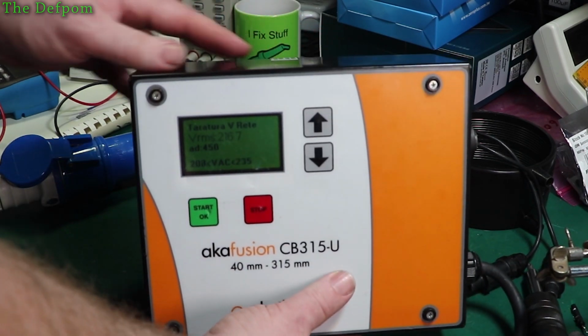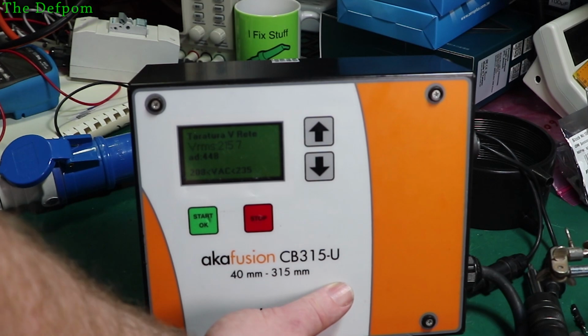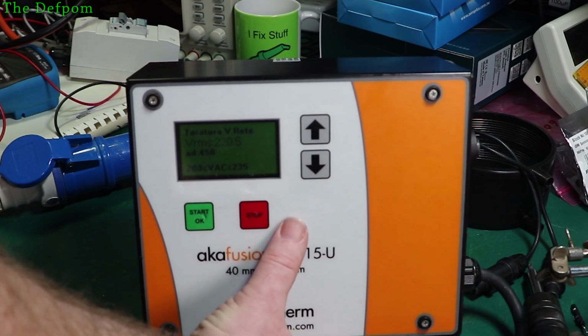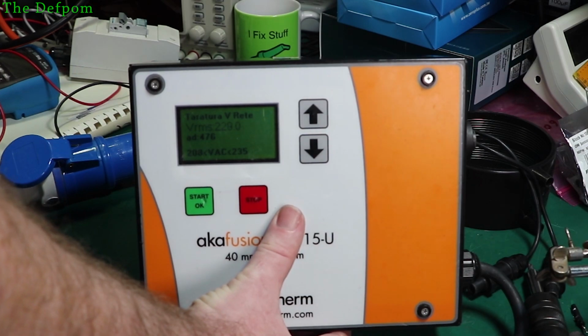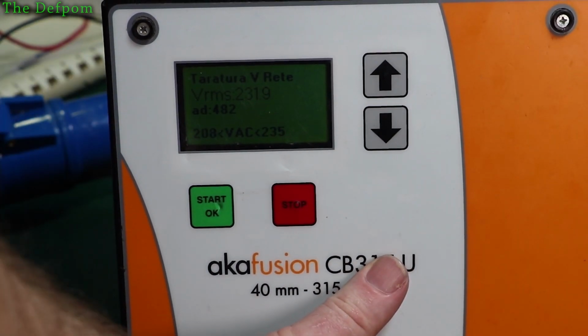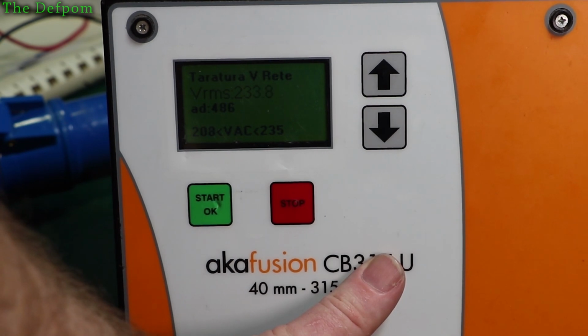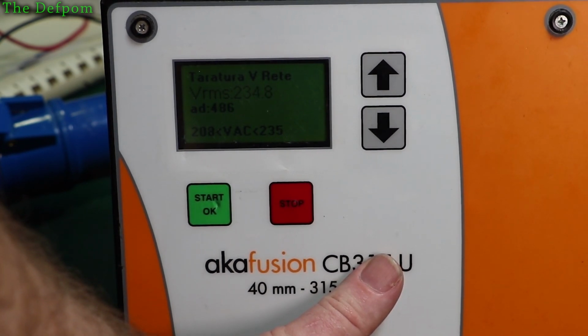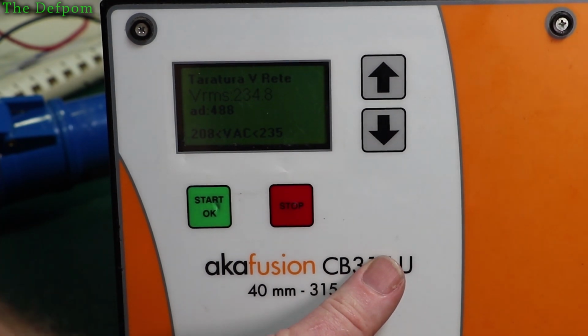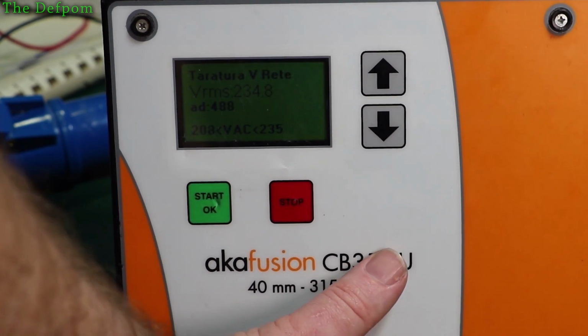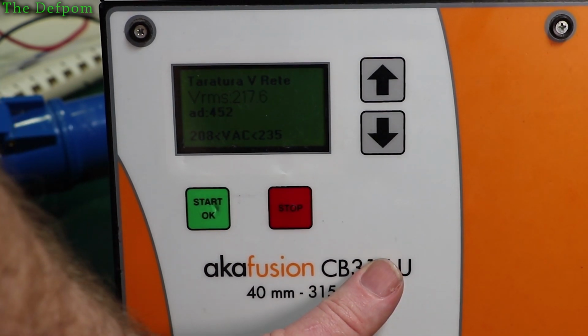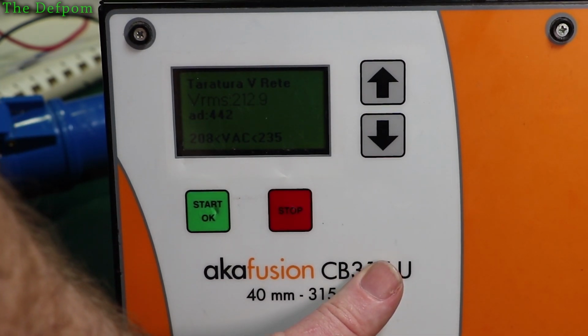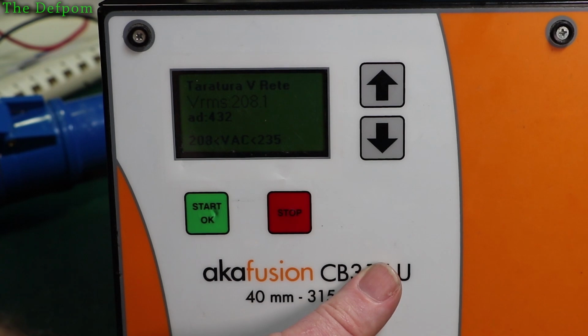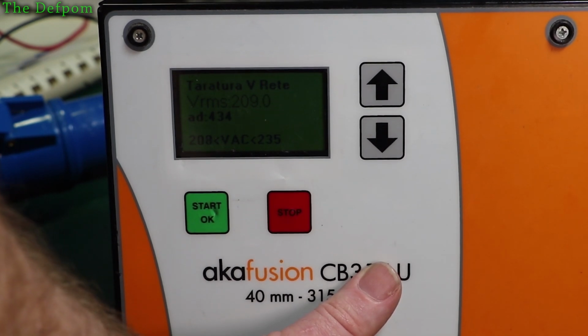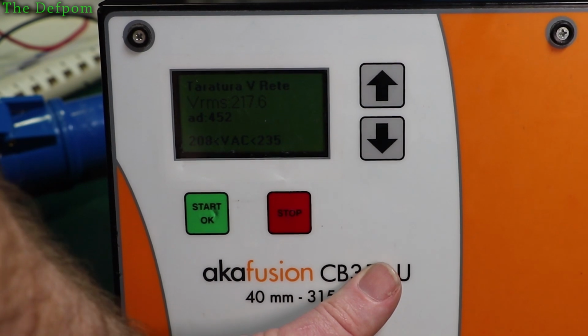I did point that one out before, that multi-turn pot is in there, blue trim pot. So if I change the voltage on here to get to the maximum it's supposed to have, which is say 235, slightly better on it. There you go. Alright, so I go up to about 235 on here, which is the maximum it's supposed to allow for. Right, it's about there somewhere. That's 250 volts AC coming in reality. If I go down to the lowest one, which is 208 on there, let's put this calibration set point there. There we go, 208. That is 222 volts coming in, or 220 to 222 coming in. Okay, so obviously it's been shifted down to make it think it's on a lower voltage when it actually isn't.